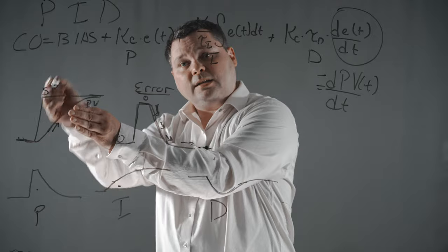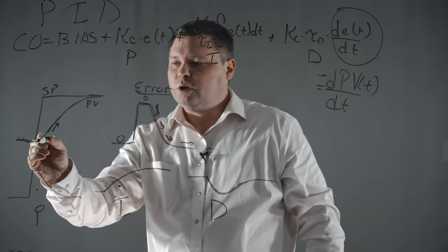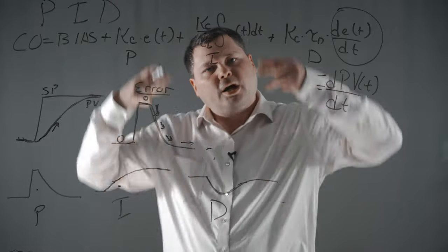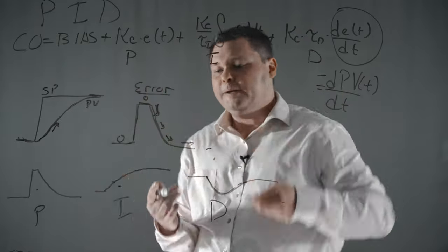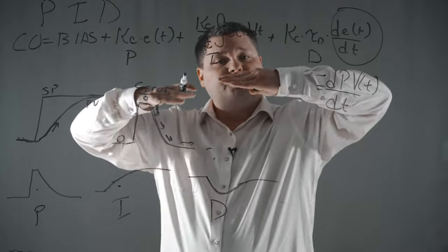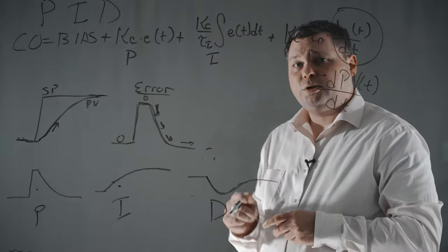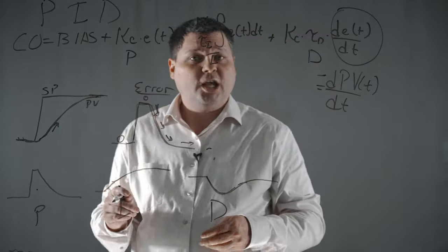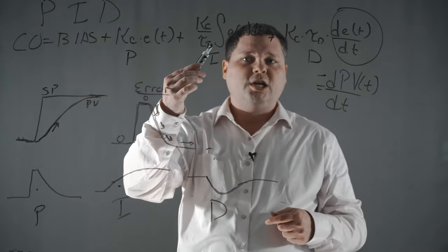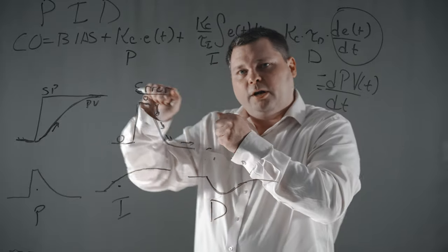Proportional provides that initial kick at the beginning to the set point change, gets that controller output moving and drives the process up. Then as my process variable gets to set point, my proportional contribution starts to pull back a little bit. The integral is starting to accumulate and shift that controller output balancing point to a new location to try to get that process variable up without any overshoot. Meanwhile, the derivative is just looking at the rate of change — it doesn't care if I'm close or far away from my target. It's just saying, 'I'm changing too much, I don't like that, so I'm going to tamp that down.' So proportional and integral push, derivative pulls back.